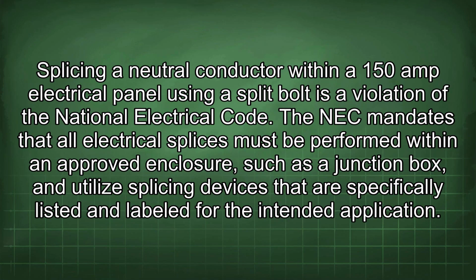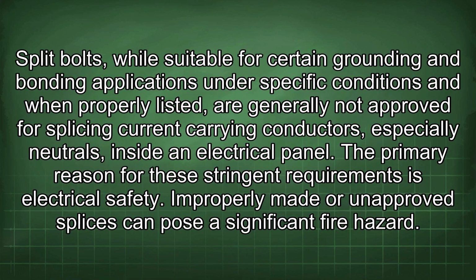Splicing a neutral conductor within a 150 amp electrical panel using a split bolt is a violation of the National Electrical Code. The NEC mandates that all electrical splices must be performed within an approved enclosure, such as a junction box, and utilize splicing devices that are specifically listed and labeled for the intended application. Split bolts, while suitable for certain grounding and bonding applications under specific conditions and when properly listed, are generally not approved for splicing current-carrying conductors, especially neutrals, inside an electrical panel.